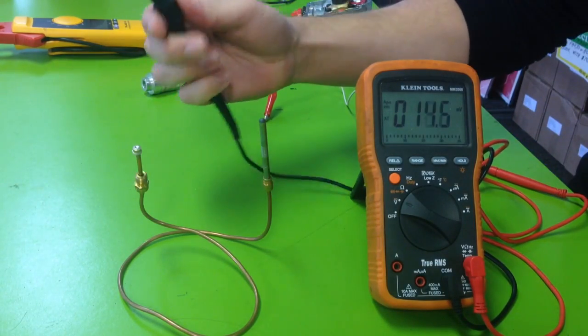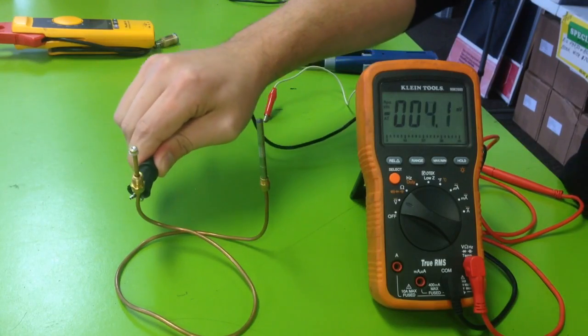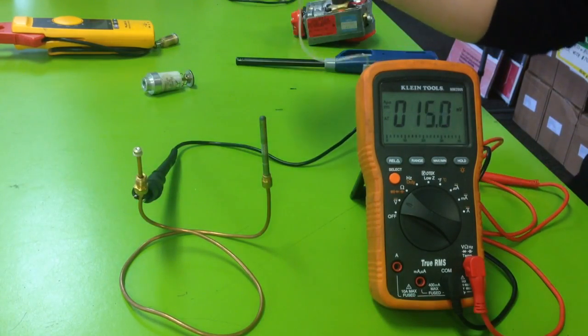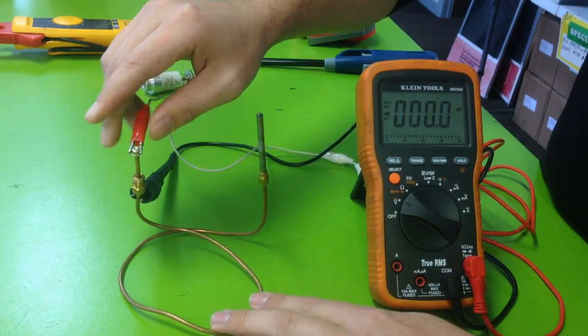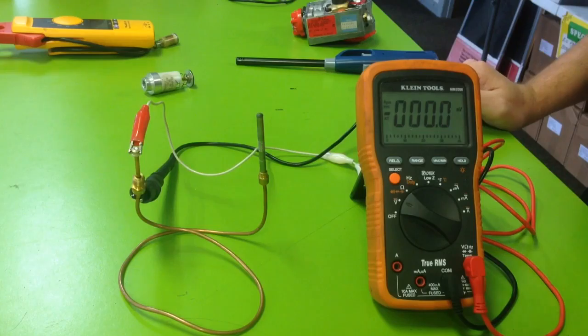You're going to take the common ground, the black lead, hook it to the copper of the thermocoupler. Then you're going to take the red and hook it to the top. You can see it zeroed out real quick there for me.